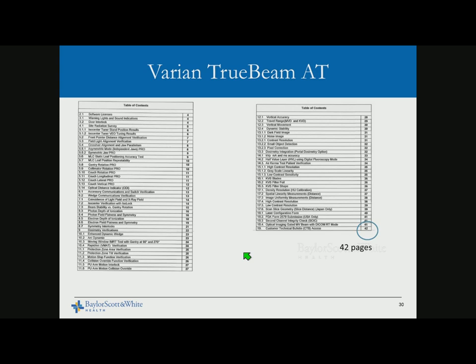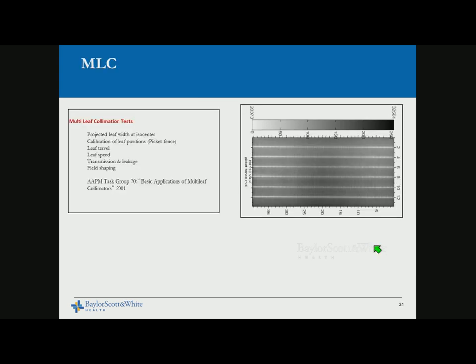For Varian TrueBeam acceptance testing, they have added new imaging component tests, but the number of pages was reduced from about 60 to 42 pages — raising questions about whether vendors are making acceptance testing more efficient while spending less time at the clinical site. MLC testing is only a functional test using Dynalog files to confirm speed limits trigger interlocks and confirm positions. We prefer physical tests like picket fence for positioning accuracy — tolerances for vendor log file tools like Dynalogs are still not well-defined.